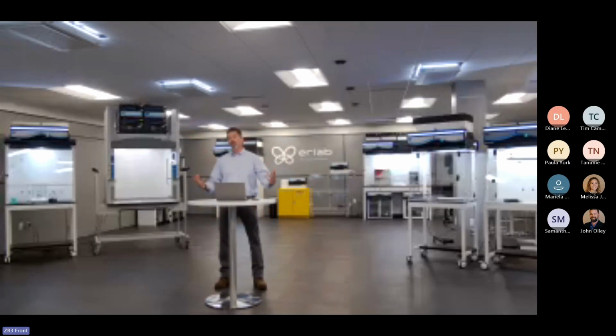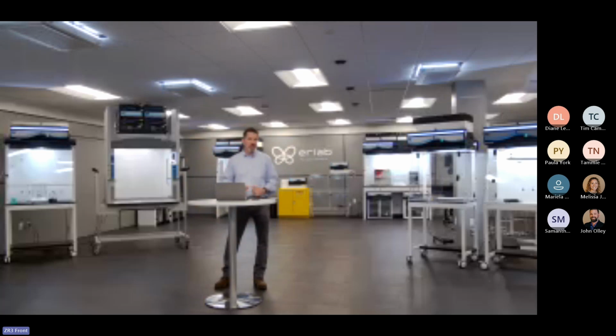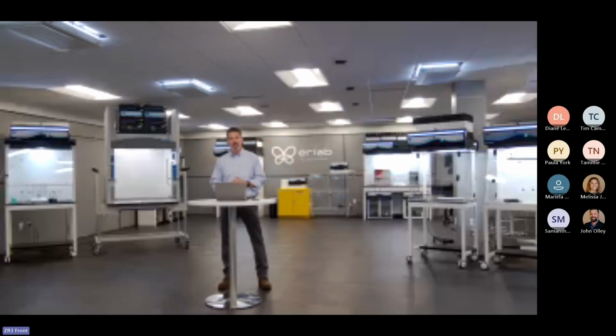It's going to depend on the size of your room, but we recommend adding about 2 air changes per hour, or the equivalent of 2 filtered air changes per hour in the space. If you let us know the size of the space, we can size it for you. But think of 1 Halo for every 400 square feet. For a 400 square foot lab with 10-foot ceilings, you're going to add about 2 air changes, so it's about 4,000 cubic feet of space. If it's twice that size, you're going to need 2 units.